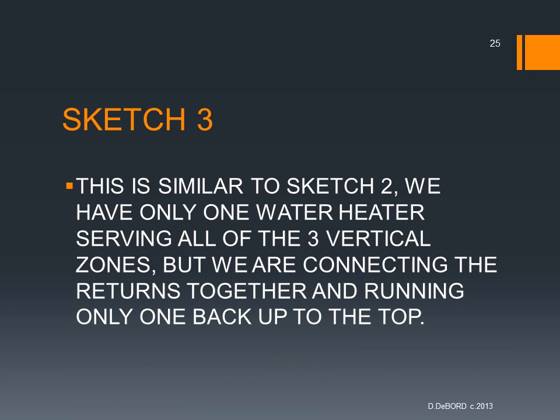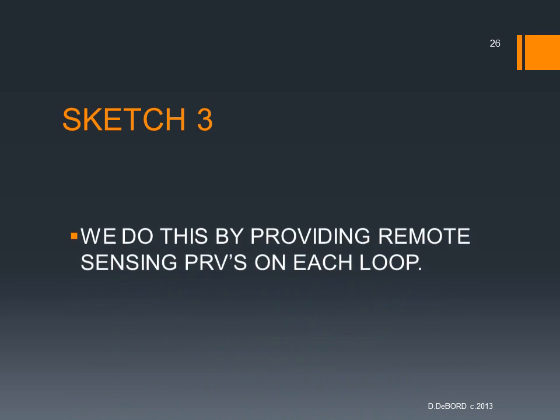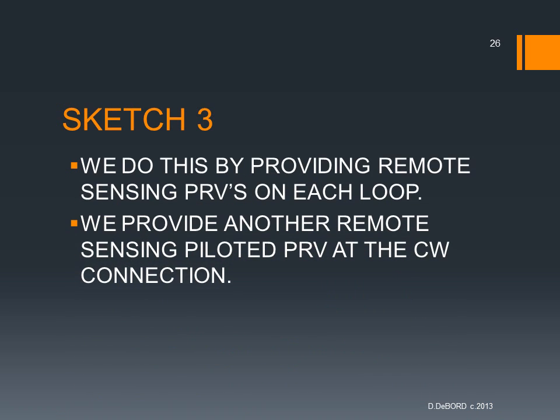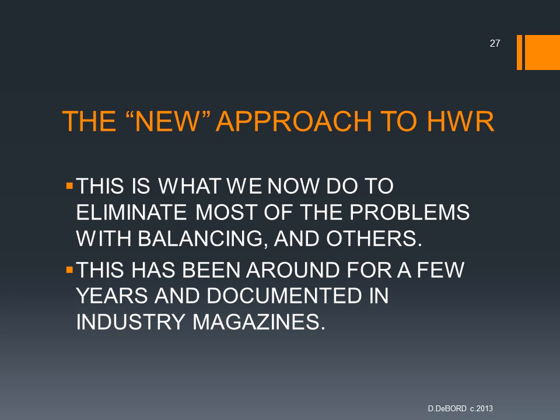It's similar to Sketch 2. We still have only one water heater serving all the zones, but we're connecting returns together and running only one return back up to the top. So that saves some piping. But the pump gets bigger, and that causes problems because we do this again by providing remote sensing PRVs on each loop, and provide another remote sensing piloted valve on the cold water connection, but we still can have balancing problems.